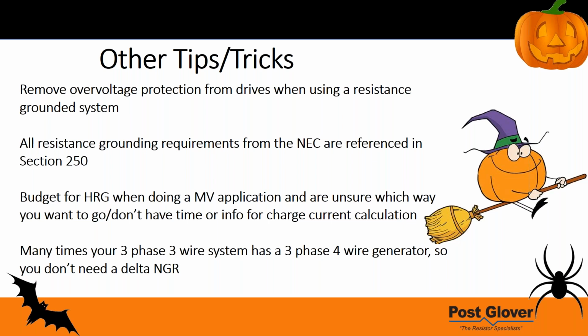All resistance grounding requirements from the NEC are referenced in section 250. Some of you who know the NEC are like, duh, section 250 is most of the grounding. But a lot of people ask me where you can reference resistance grounding, and I can point them to 3 or 4 different sections - most are in 250, some in 311, there's a 367, it doesn't matter. My point is, all the information you need is in 250, either referenced there or contained there. If you want to know just one number for resistance grounding, that's the one to remember.